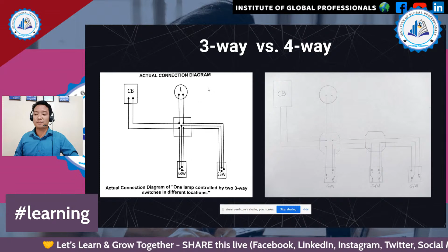And this is one of the most expensive types of electrical wiring connection in the industry, because you will be using the four-way, which is one of the most expensive switches to be bought. And if you're going to install it in 6 locations, for example, you can just add four-way switches, but the two three-way switches should be retained, because it will not light up if the two three-way switches are removed.